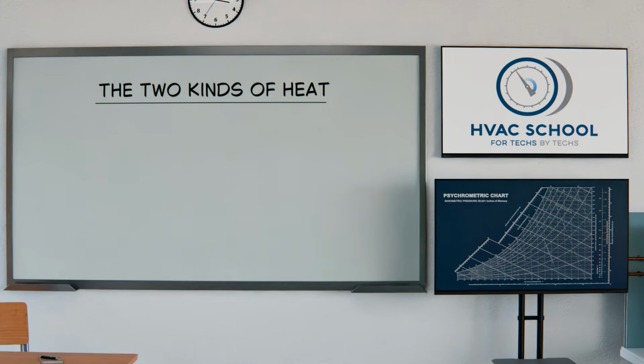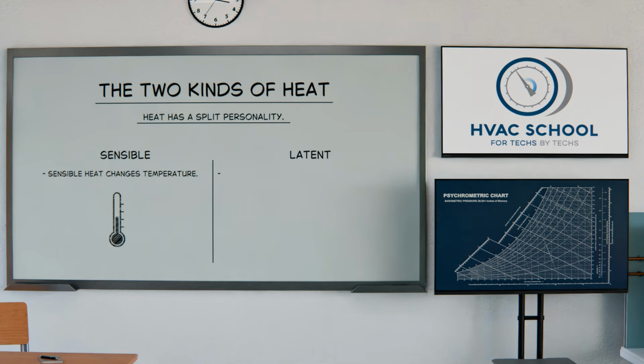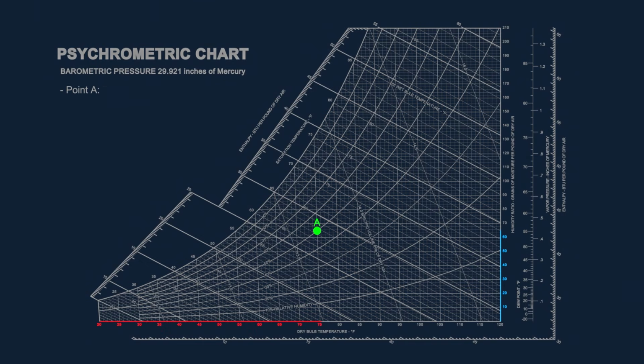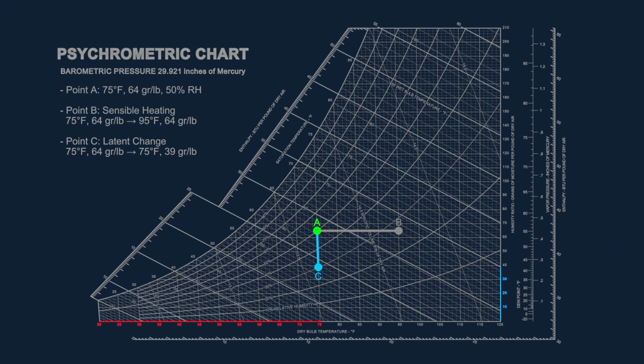All right, let's talk quickly about the two kinds of heat. And if there's one thing that the Psych chart makes perfectly clear, it's the split personality of heat. Sensible heat changes temperature, and latent heat changes moisture content. When you warm air with a heater, you move horizontally to the right, pure sensible change. When you remove moisture with a dehumidifier or cooling coil, you drop vertically, latent change.